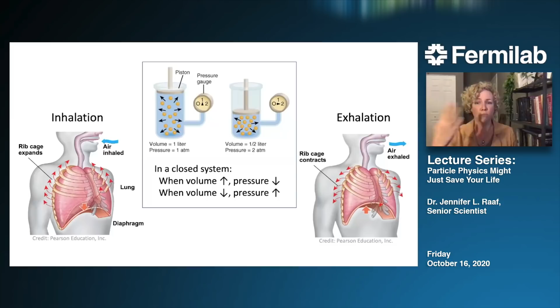So let me tell you about two of the ways that you can create pressure difference to get the air in and out of your lungs. When mechanical ventilators were first invented, the most common type was called negative pressure ventilation, which is what you see on the left. So in this case, the patient's body, whole body, or sometimes just the chest, although hopefully not cutting him in half to do that, is inside some closed box. And the head is outside the box. So if you pump the air out of the box, then the pressure inside the box is decreased relative to the ambient room pressure. And then the air will flow into the lungs to equalize that.